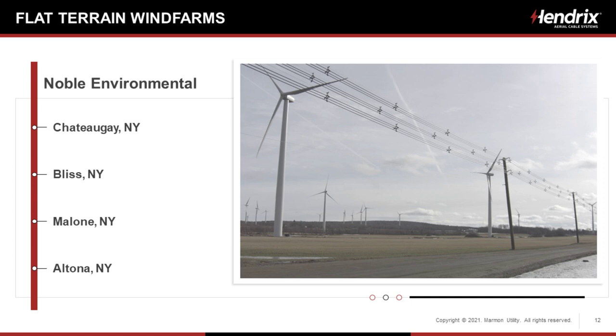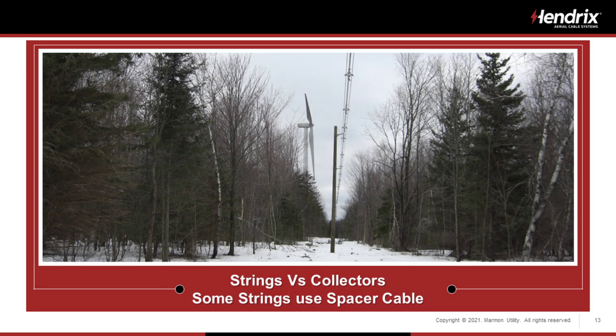So here we used the 556 kcmil, and we put between 8 and, I want to say, 12 or 13 1.5 megawatt turbines on each collector. Now, we could have gotten a lot more megawatts on each collector, but these ran several miles, so they were concerned about voltage drop and losses. But we can get into that when we help you design these facilities.